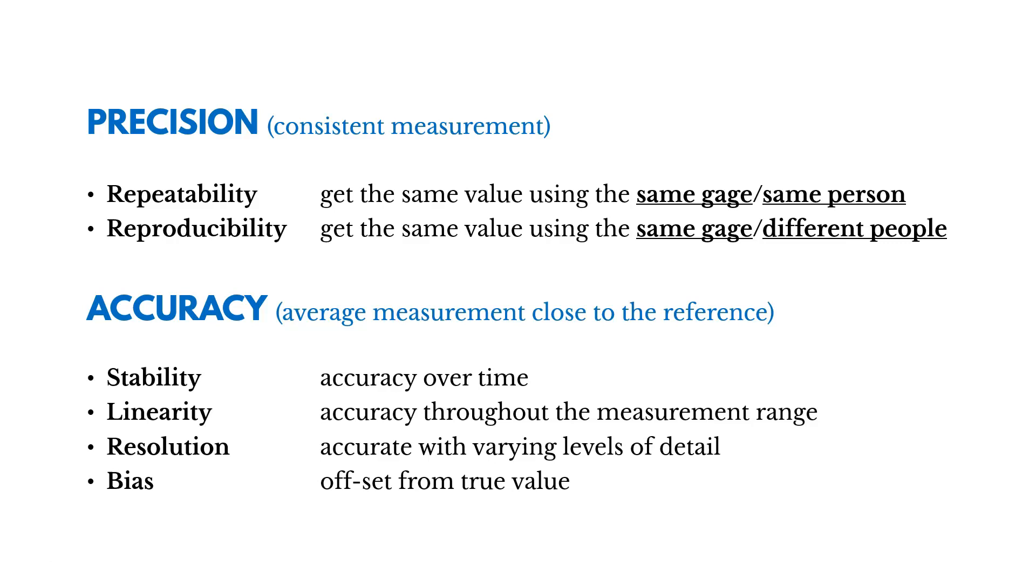Now, with accuracy, we seek for stability, getting accuracy over time. And then linearity, getting accuracy through the measurement range. So an example of this is we would hope that a thermometer, if we're measuring temperature, is accurate in both low and high temperatures, so across the range. Then resolution, we're seeking for accuracy with varying levels of detail. And then something we're trying to minimize here is bias, being offset from the true value. So an example would be that all measurements are off by 5% or 10%.